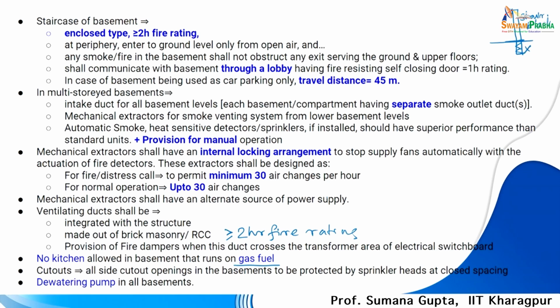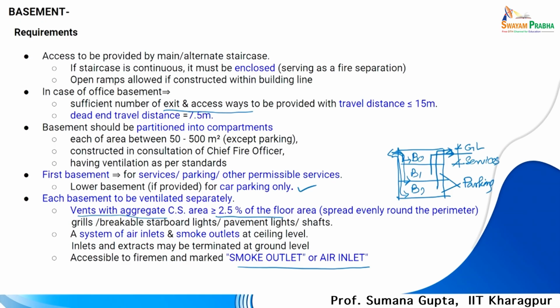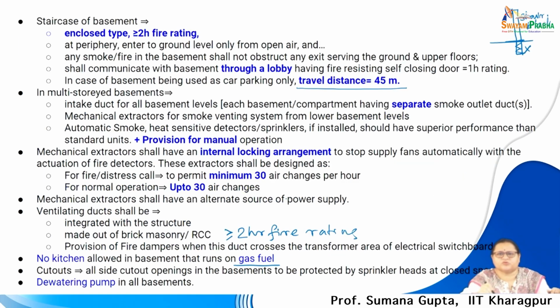Now, you see, in case of basements being used only for car parking, the travel distance is 45 meters. Though we saw in the previous slide that the travel distance should be within 7.5 meters from the dead end or 15 meters, in the case of lower basements meant only for parking, the travel distance can be up to 45 meters.